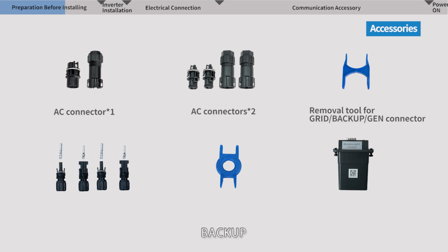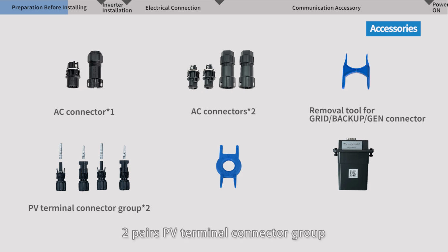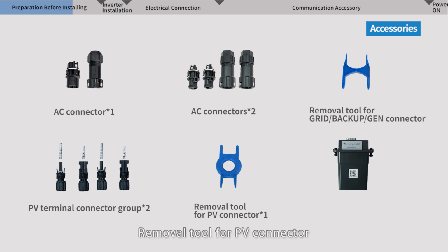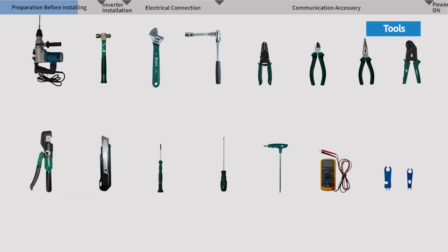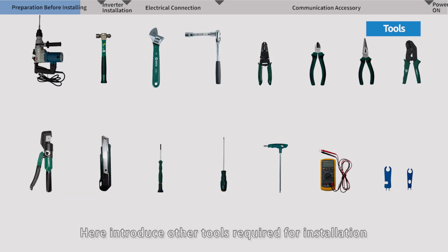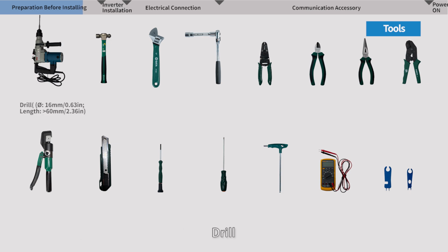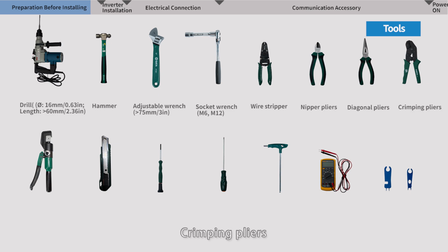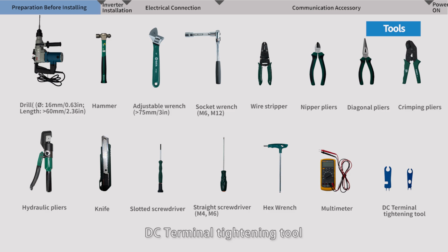Removal tool for grid, backup, and gen connectors. 2 pairs PV terminal connector group, PV positive, PV negative. Removal tool for PV connector. Wi-Fi dongle and some documents. Besides, here we introduce other tools required for installation: drill, hammer, adjustable wrench, socket wrench, wire stripper, nipper pliers, diagonal pliers, crimping pliers, hydraulic pliers, knife, slotted screwdriver, straight screwdriver, hex wrench, multimeter, DC terminal tightening tool.